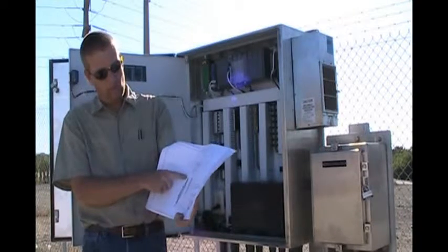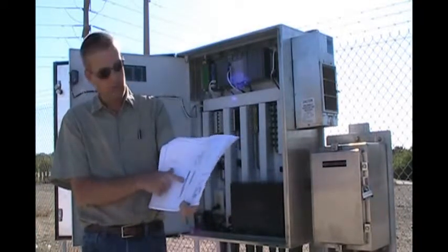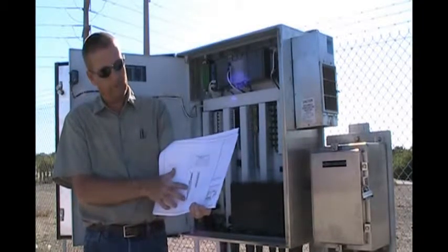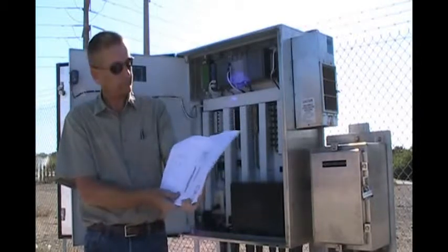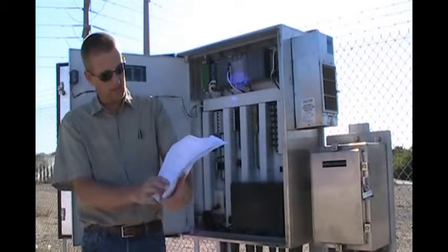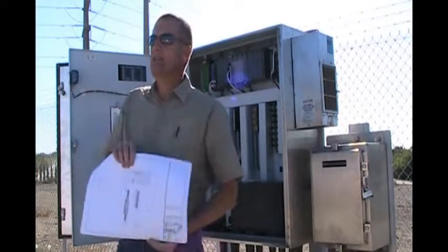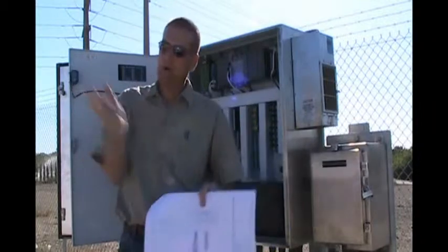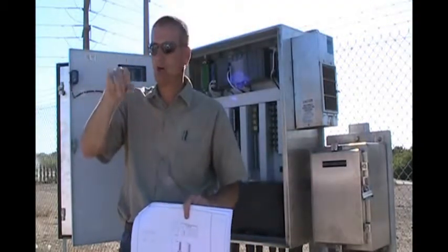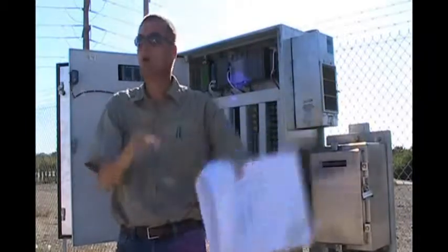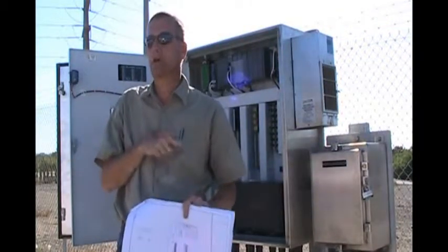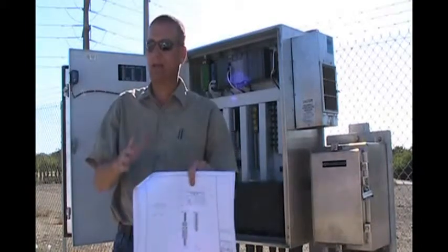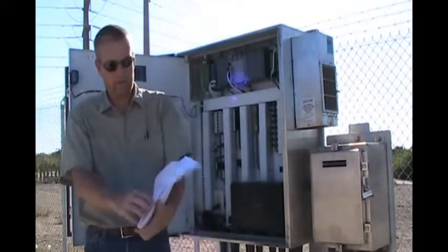So here's the layout of the Savaine panel. You'll have, once again, the top part, your power distribution. Then you'll have digital termination here and your analog termination there. The panel is very small. It's Savaine's main RTU panel, and the solar panel is a separate panel. The batteries, the solar charger, everything solar is in its own panel. At the RTU with the level transmitter, which is LT 2005, the solar and the radio are in the same cabinet. Okay, so that's one big difference.